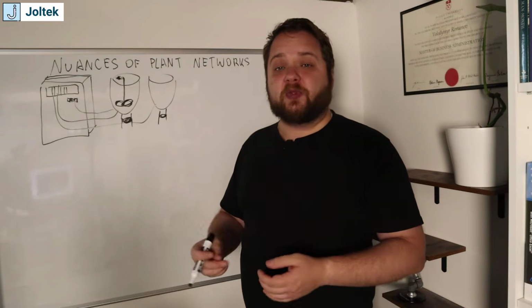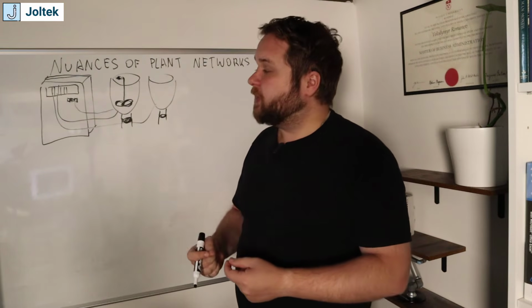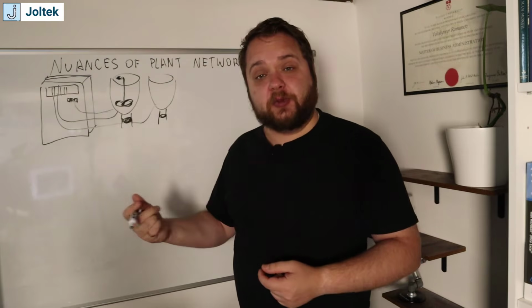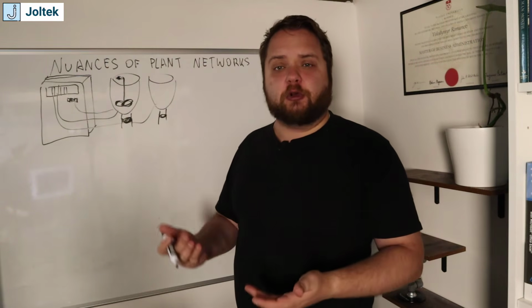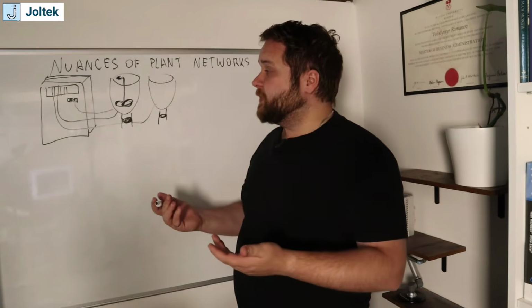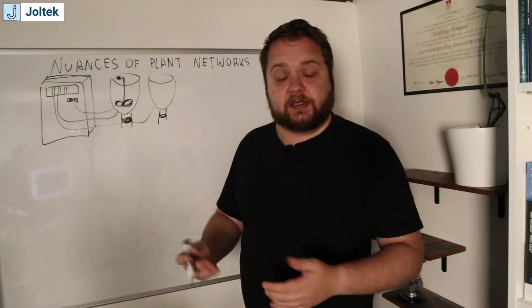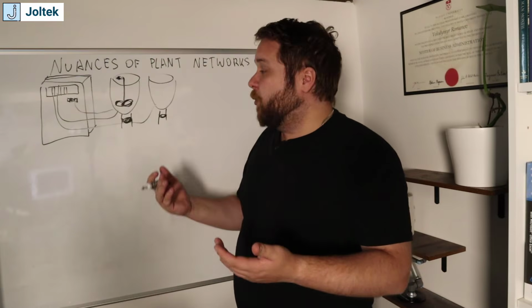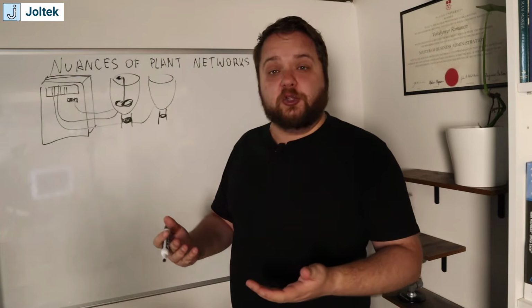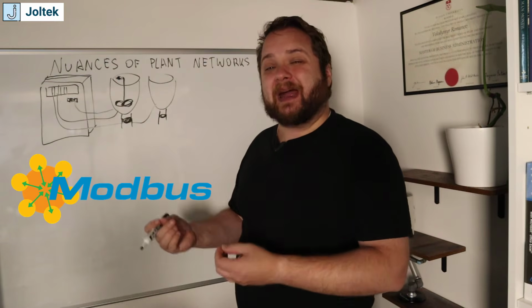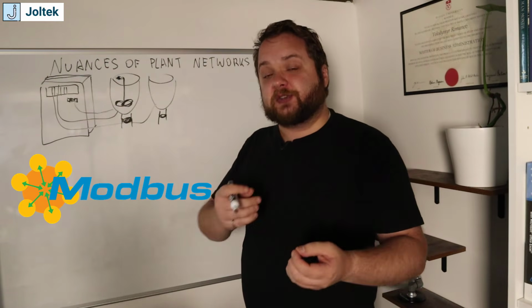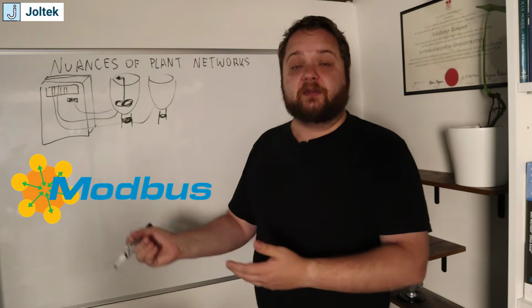And that basically meant that we needed to pass information from the PLC to the device and from the device to the PLC. And that is how some of the earlier protocols were born, and you can still purchase devices that utilize some of those protocols. And one of the most common ones, I would argue, would be Modbus.